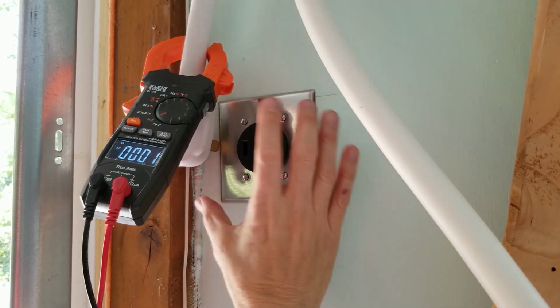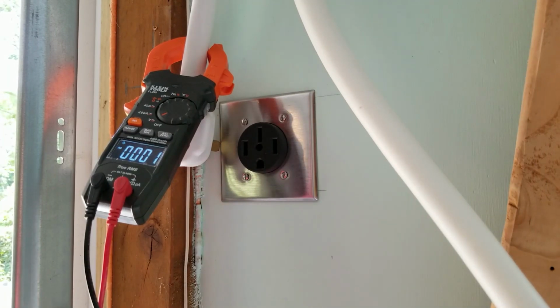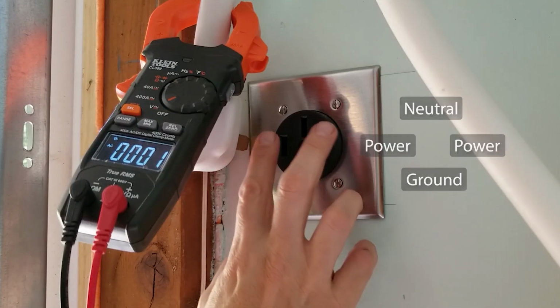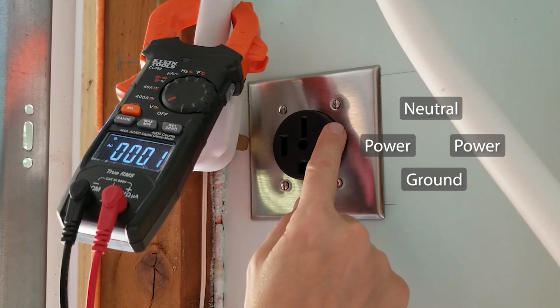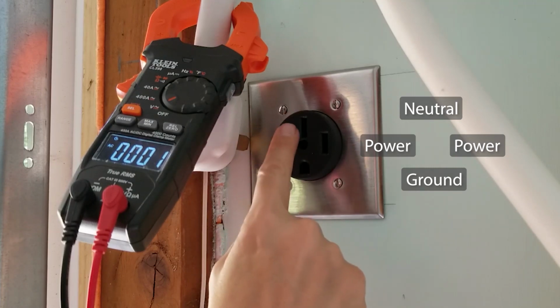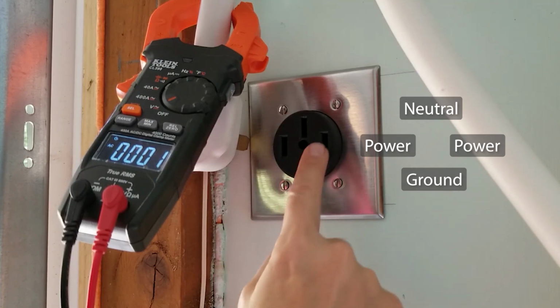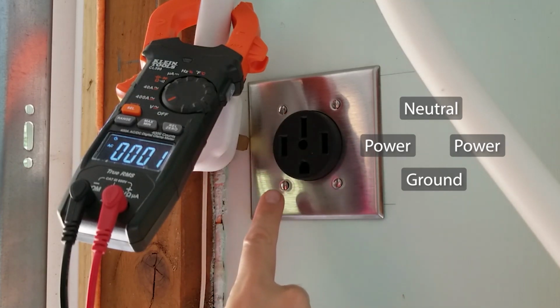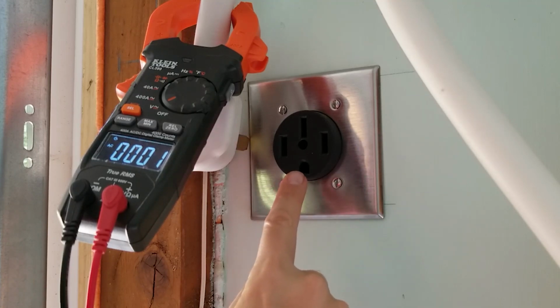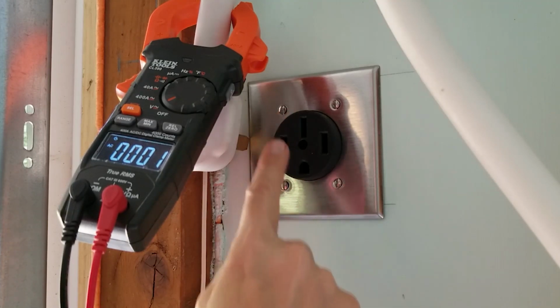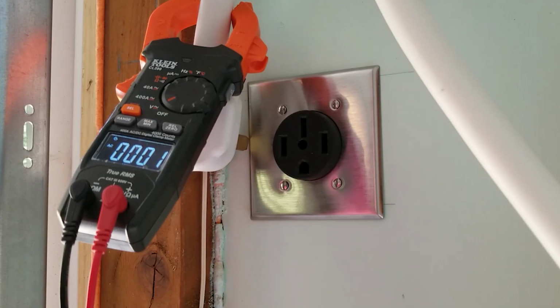So we know this circuit is correctly wired up and the receptacle is also correctly wired up because everything is where it should be: 220 across, 120 to each of the legs going off the neutral, same thing going off the ground to each of the legs, and then there should be no difference between neutral and ground.